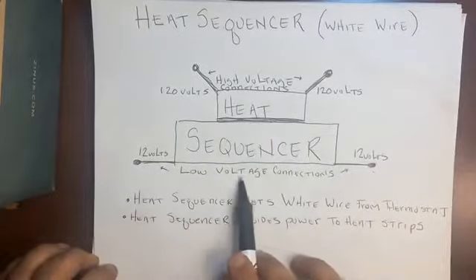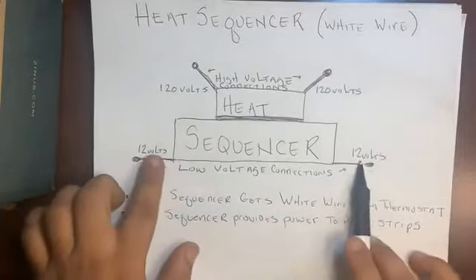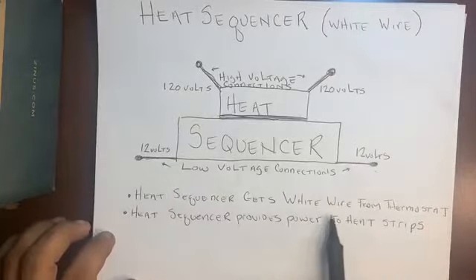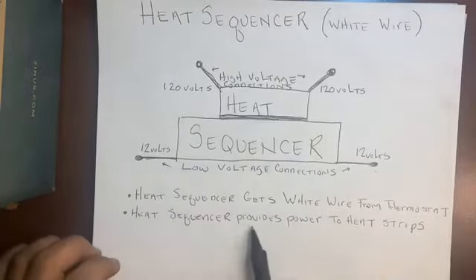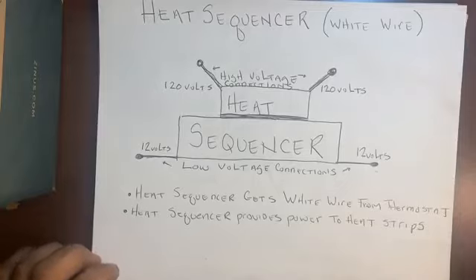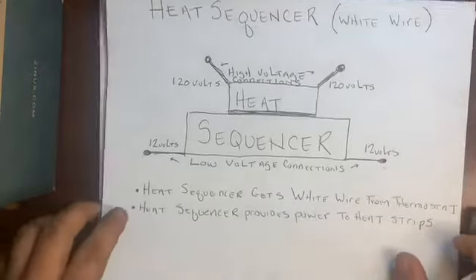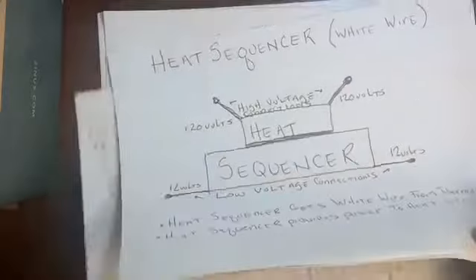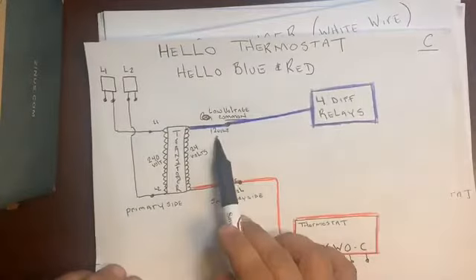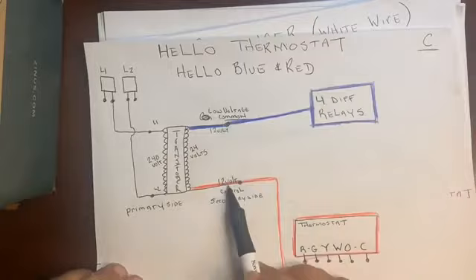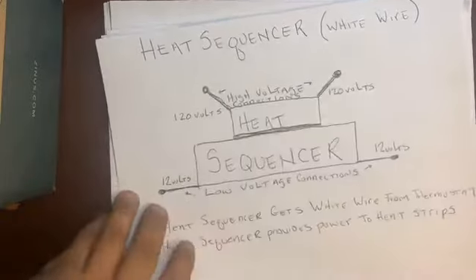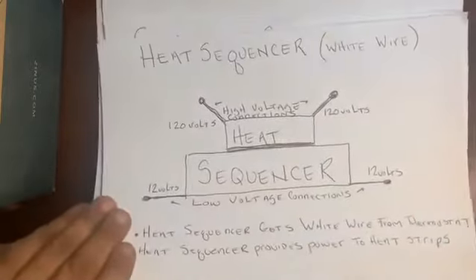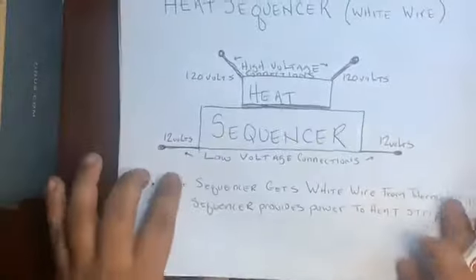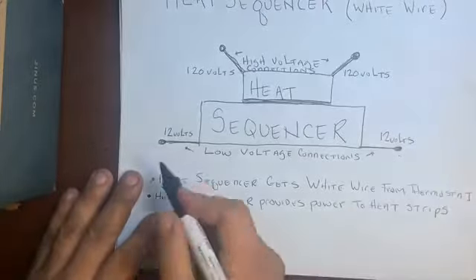Heat sequencer has low voltage connections along the bottom, the base. The heat sequencer gets the white wire from the thermostat. The heat sequencer provides power to the heat strips. Now, as we learned in the previous lesson, we're always gonna have our 12 volt low voltage common and our 12 volt control, okay? Every relay has two hands. If you look, every single relay has two hands for the low voltage. So one side is gonna be our low voltage common.